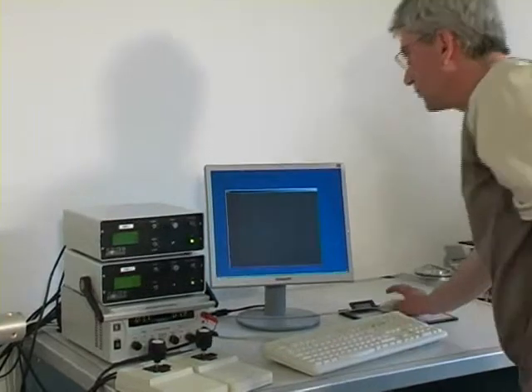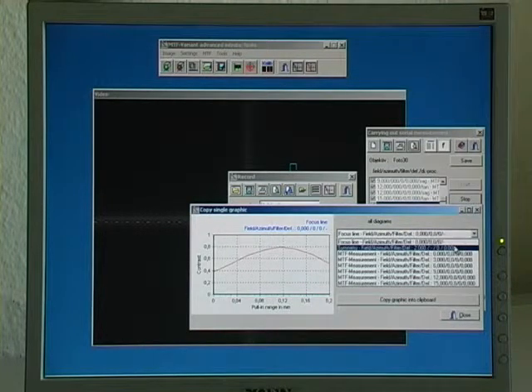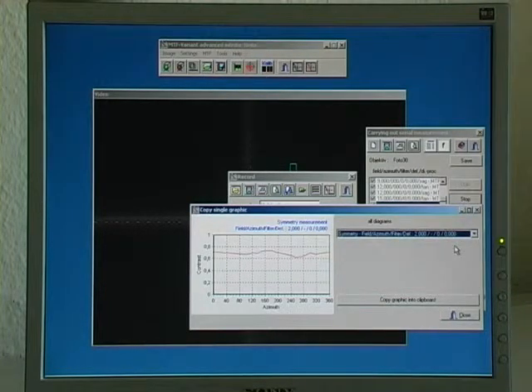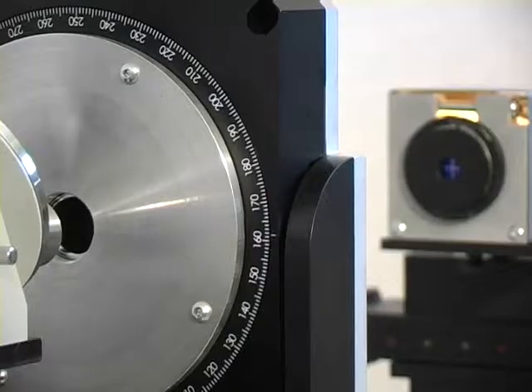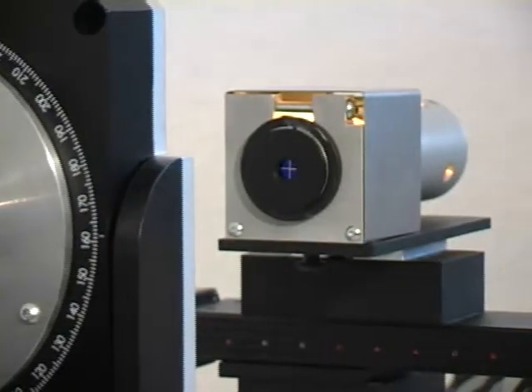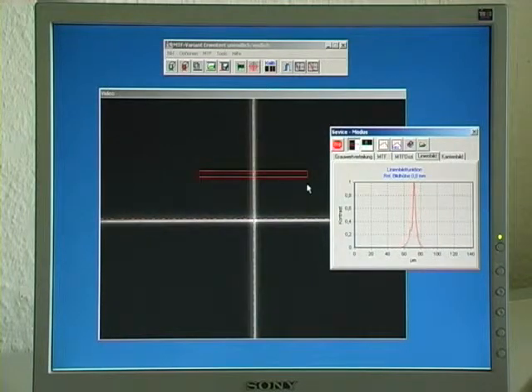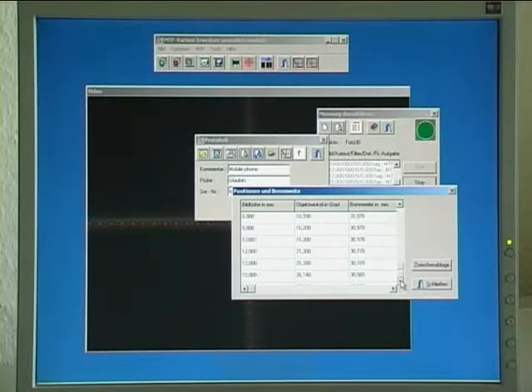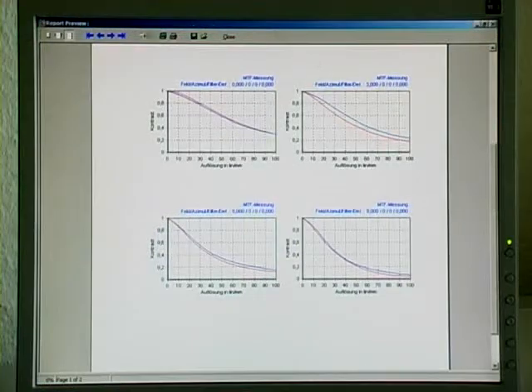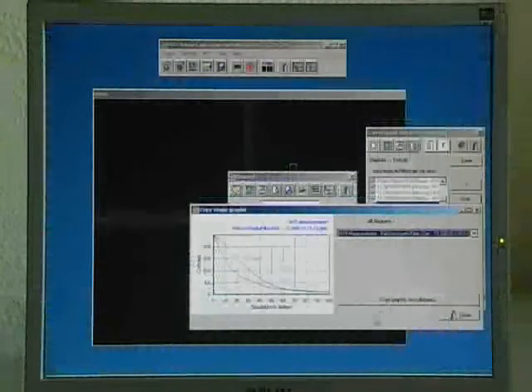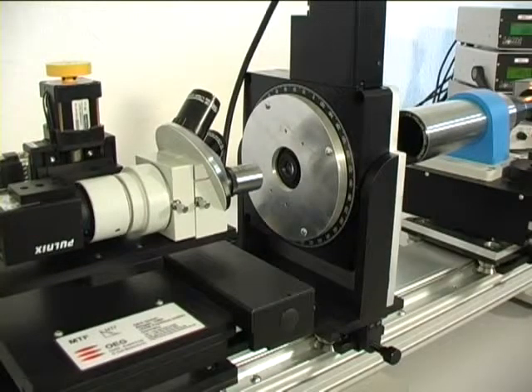Fully automatic measuring sequences can be programmed by the operator very easily, combining any order of all existing measuring options freely. In addition to the MTF, the following data can be measured: line spread function, edge spread function, effective focal length, distortion, astigmatism, and imaging scale. All measurements are performed in real time using the live video image, with different possibilities for the presentation of results.